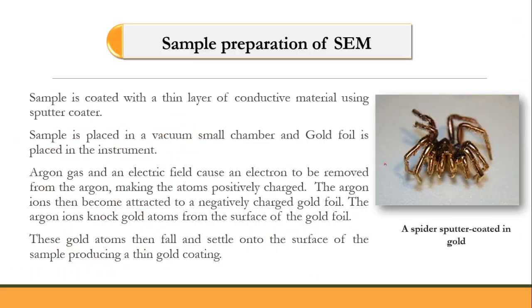For SEM sample preparation, the sample is coated with a thin layer of conducting material. If the material is not conductive, you must coat it with a conductive material — normally gold is used for that purpose, though aluminum can also be used. Here you can see a spider that has been sputter-coated in gold, ready for SEM analysis.